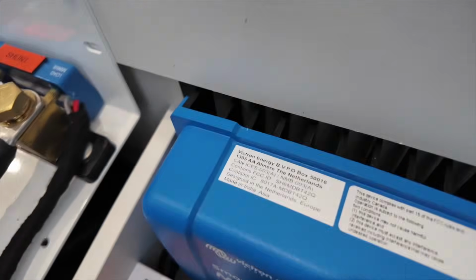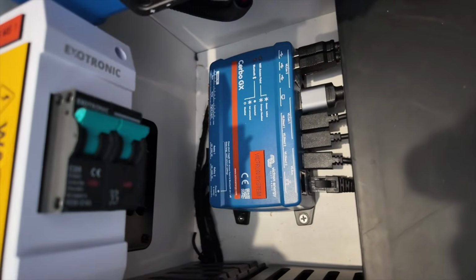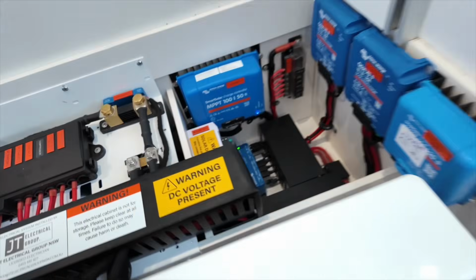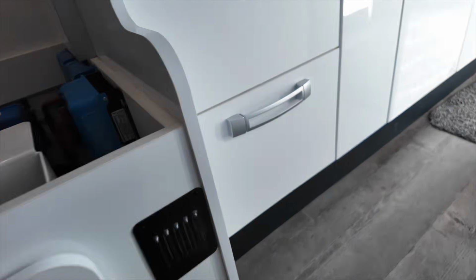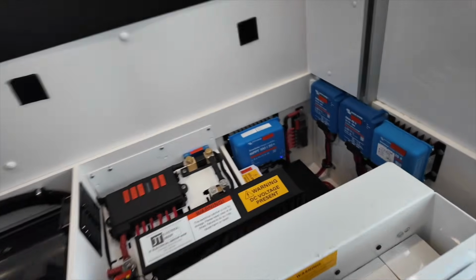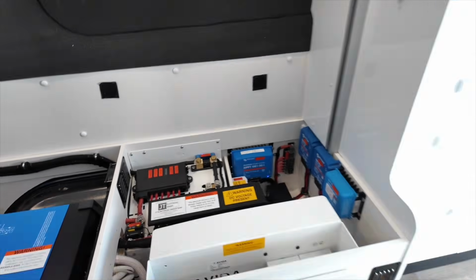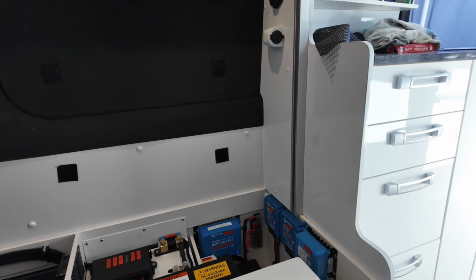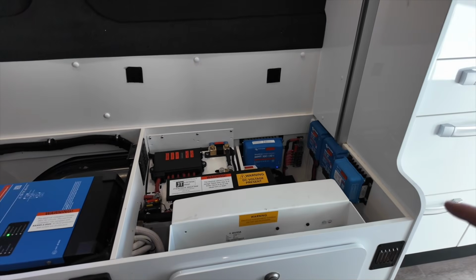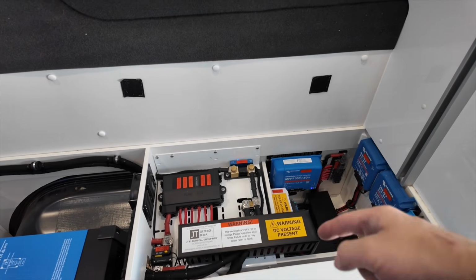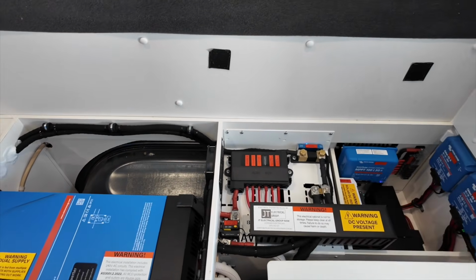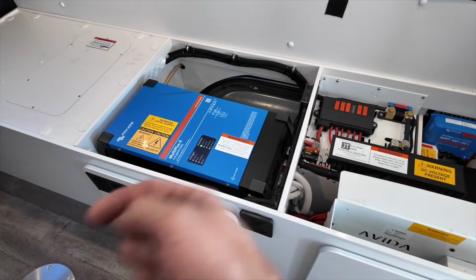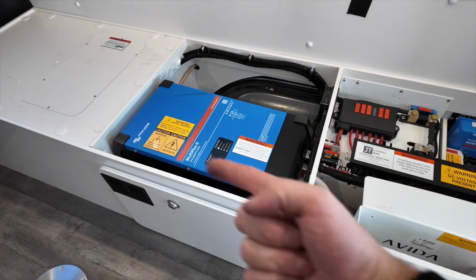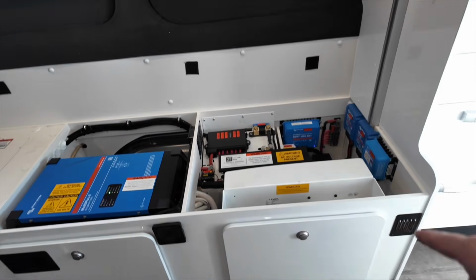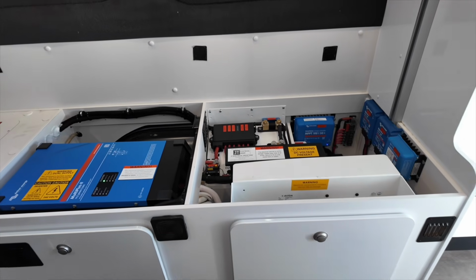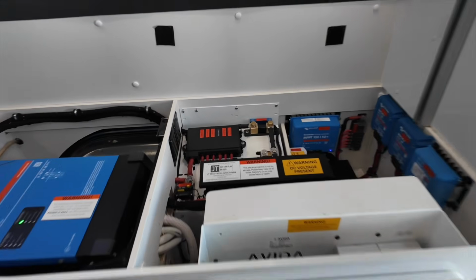We've got another vent underneath the solar circuit breaker, and then you've got another inlet here with no fan just because it wouldn't fit. But all this cooling system is controlled off the temperature sensor behind the DC charger, so it's in a good spot. And you got inlet air here, you've got another vent under there, a fan here sucking air that way, and then 2 fans here sucking air both out, and then the multi-plus's fan will push air that way to come out. So you're going to have a nice air cooling system of inlet and outlet through this electrical cabinet.